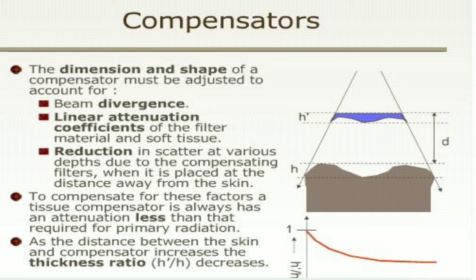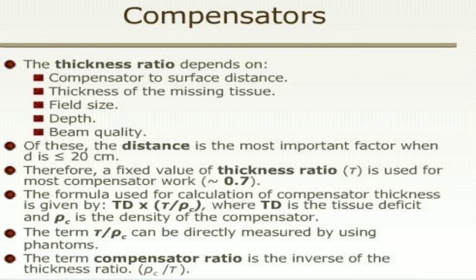To compensate for these factors, a tissue compensator always has an attenuation less than that required for primary radiation. As the distance between the skin and the compensator increases, the thickness decreases. A thickness ratio depends upon the compensator-to-surface distance, thickness of the missing tissue, field size, depth, and beam quality. The term compensator ratio is the inverse of the thickness ratio.